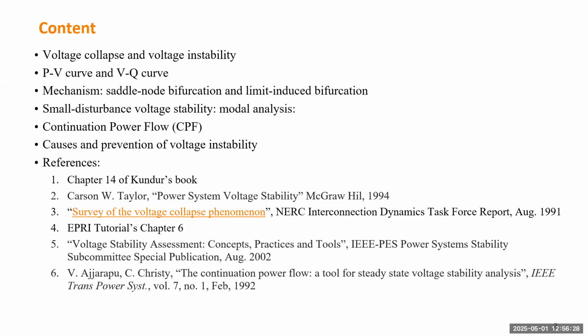So if you work for any power company or do some research for power systems, and if you want to address some stability issues, I would say maybe 80% of stability issues will be voltage stability issues, not the small signal stability or transient stability problem. Because the small signal stability and transient stability problems are mainly caused by designs. So if your system has good damping, or you place power system stabilizers to improve the damping, you won't see many oscillations. Even if there's oscillation, it can be quickly damped.